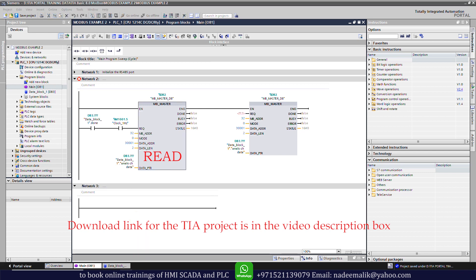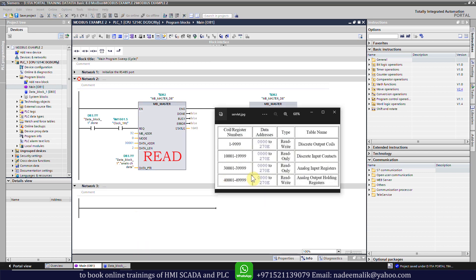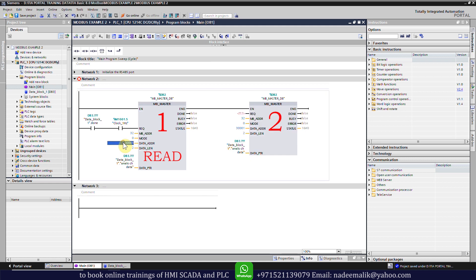If we look at the data register table for Modbus communication, we can see that the registers for discrete input contacts start from 10001. So we will enter 10001 in the data register input to read the status of the switches connected at the input terminals of the IO module.